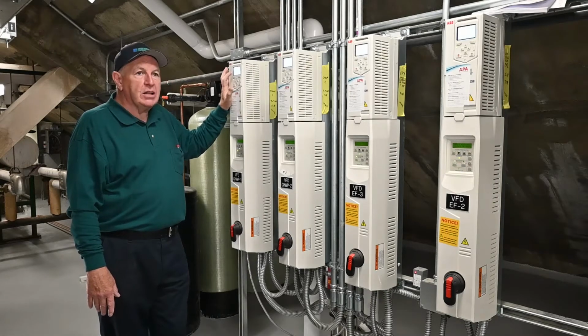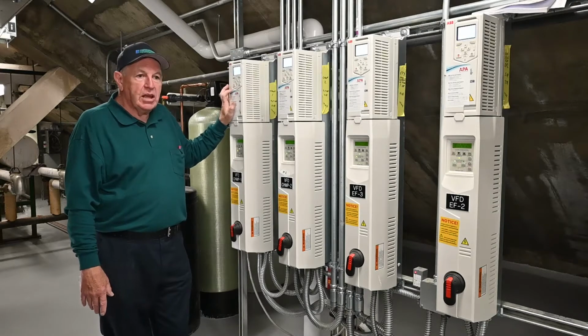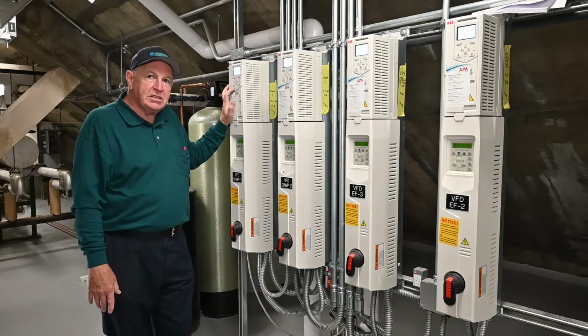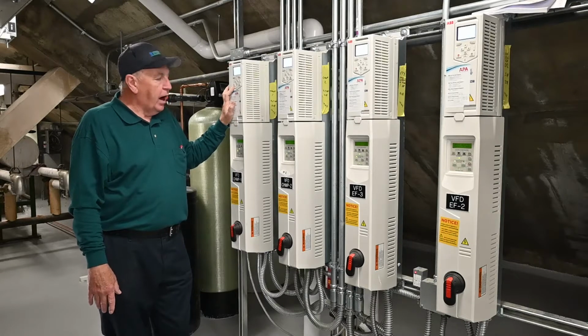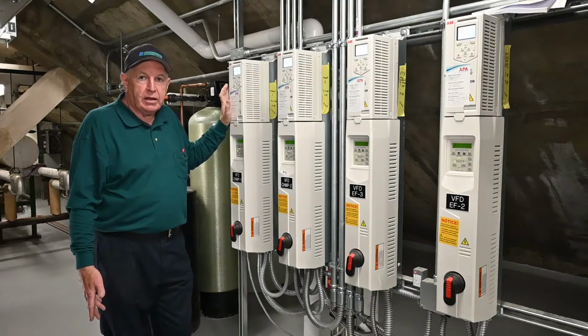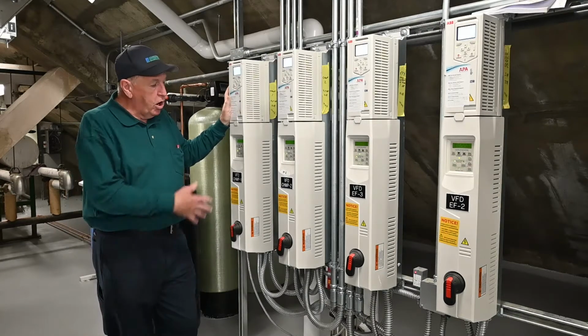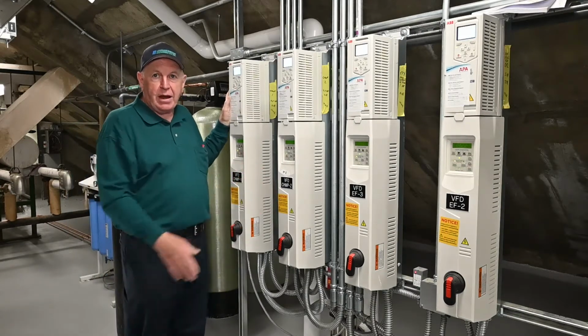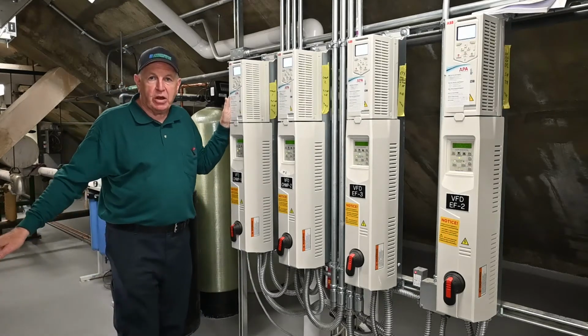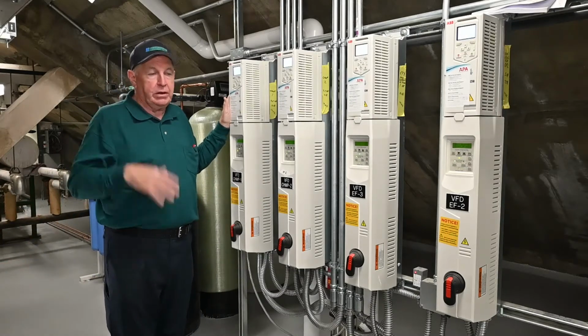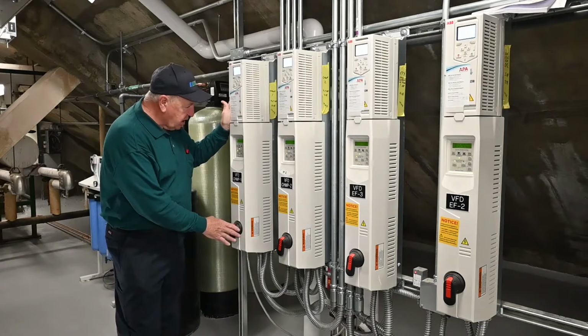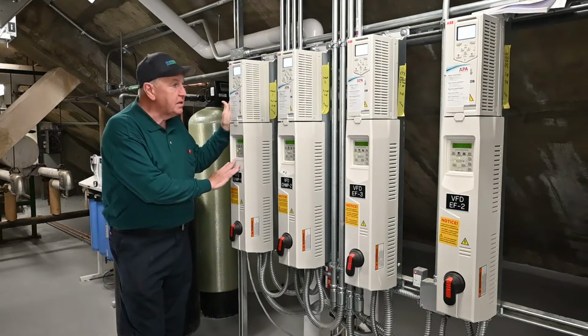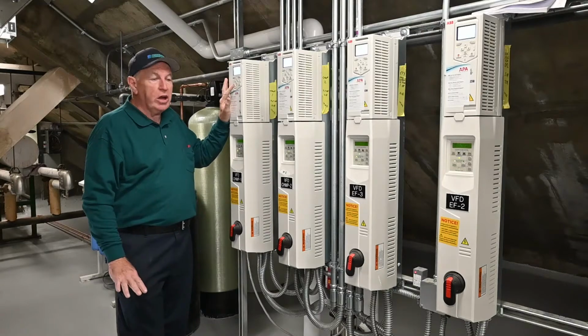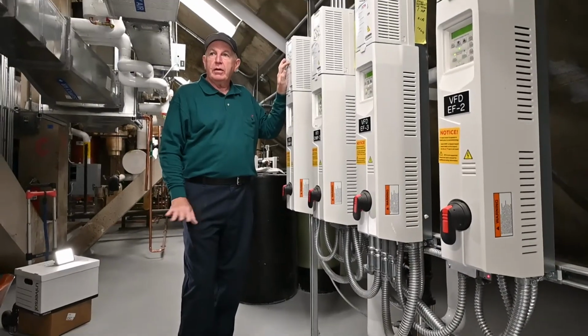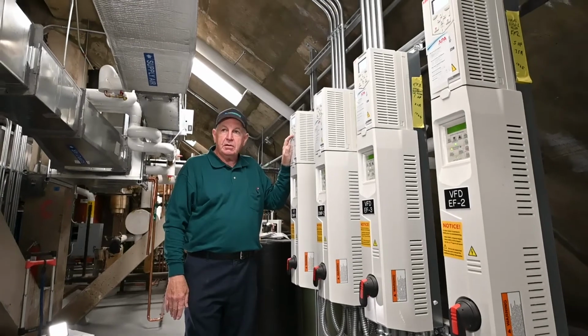If you have a fault here, the only way to reset the fault is the red off button, which is the reset. Then when you're done with that, you press auto, and it should return to automatic. If that doesn't happen, it should automatically swap over to the other pump. That's part of the BMS training, and that's out of my realm. But these are the drives. There's a disconnect switch. There's an automatic bypass, and typically all you want to see is auto, and that's it.